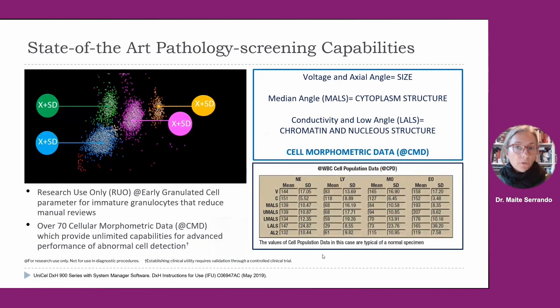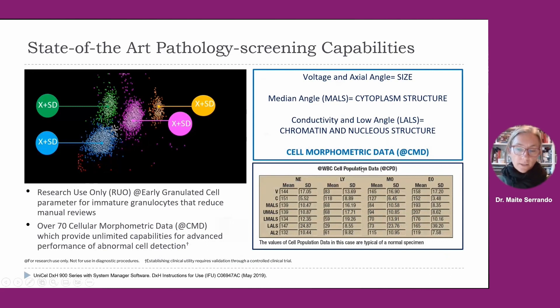Let's talk about the state-of-the-art pathology screening capabilities of this analyzer. First, the research-use-only parameters, such as early granulated cell. This parameter detects immature granulocytes, reducing the need for manual reviews in many cases and patient types. We also have over 70 cellular morphometric data points — called in the scientific literature cell population data — providing unlimited capabilities for advanced detection of abnormal cells. We can relate voltage and axial angle measurement to cell size, median angle measurement to cytoplasm structure, and conductivity and low angle measurement to chromatin and nucleus structure.